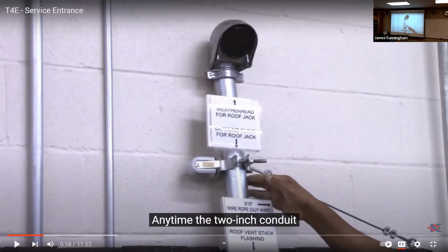So here in Santa Barbara, on some of the older homes, you might see a 1-inch mast, you might see a 1.25 inch mast. The new code for your mast is 2-inch. So you have to have at least a 2-inch mast coming out through your roof. If you're doing underground cable, you have to have a minimum 3-inch PVC conduit to run your wires underground from the power pole to your panel. So Edison requires a minimum of 3-inch, sometimes depending on the size of the service or the distance, they might require you to do this in 4-inch, which is really huge for when you only have 3 wires coming in.